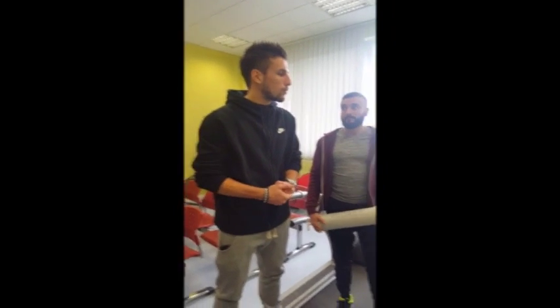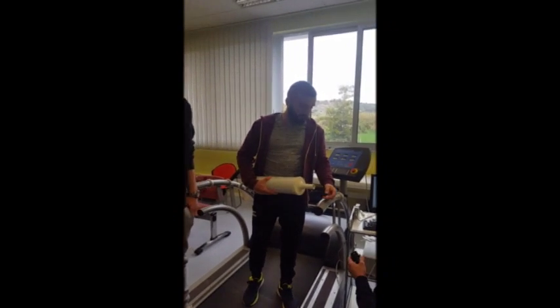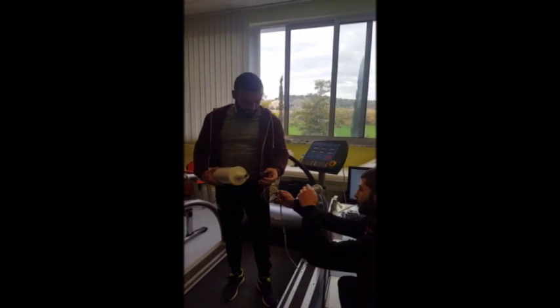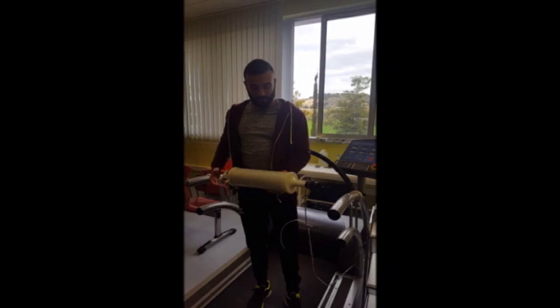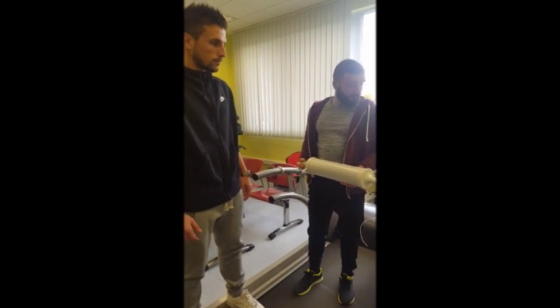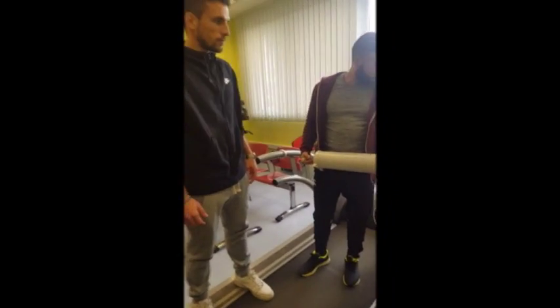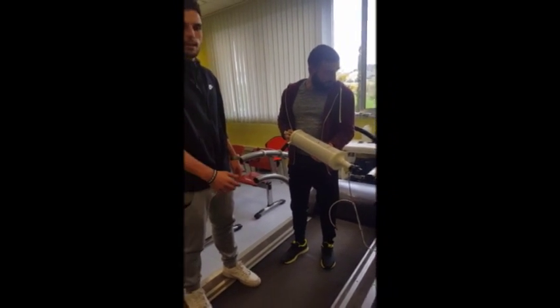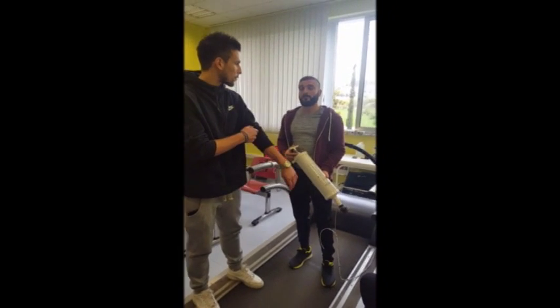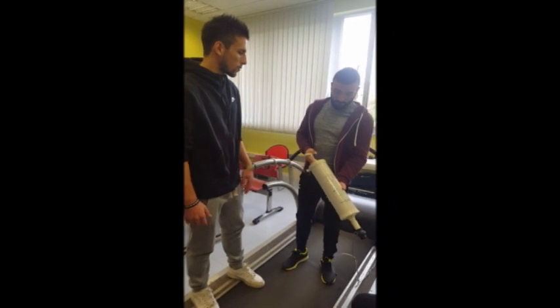After approximately 3 to 4 minutes, the calibration of the sensors is finished, and now we do the turbine calibration. So first of all, you have to insert it inside. And now when he presses test, okay. Approximately he needs to make this procedure about 10 times, so 3 liters of air will go in and out. So now you can start with this.